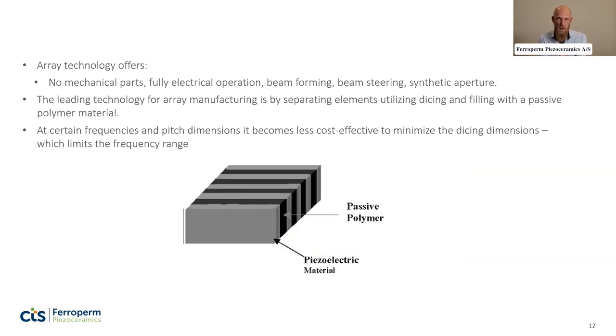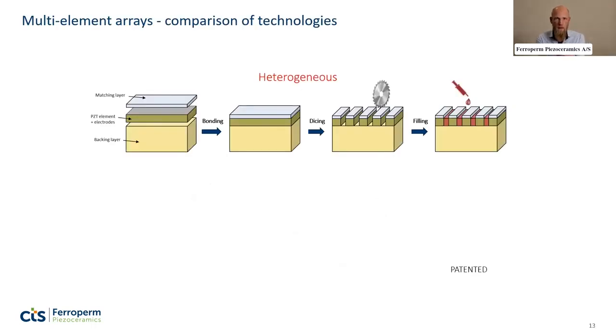And so this was about a single element transducer using thick film, and of course the next application you would have in mind is, why not make arrays? So this is something that we worked on as well. If we think about the conventional way that arrays are made for high and low frequency, is that you have some kind of assembly process with the discrete components. There's a backing layer, there is a PZT element, and then electrodes, obviously, and then a matching layer. So this has to be individually manufactured and then assembled somehow through a bonding process. Then you can dice it up to make your composite usually, or to make discrete array elements.